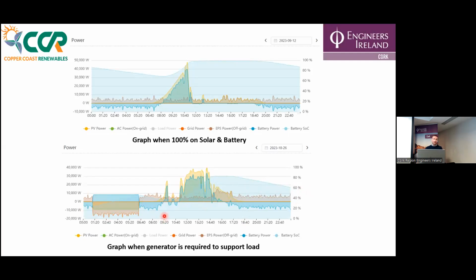Sometimes in late December, early January, the generator is going to kick on twice a day. That's because the batteries are going to charge up to 40%, discharge to 20, and then it's going to kick on again because we're going to have less solar hours. But we're going to monitor it. We may change the 20% safety band down slightly to extend it, but until we see how the system is performing, it's very hard to model when your heat pumps turn off on temperature, and offshore they get a breeze, they could go on. So we have it modeled as best we can.